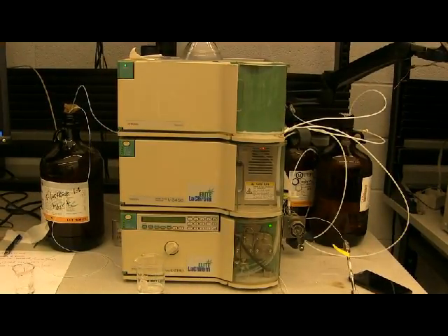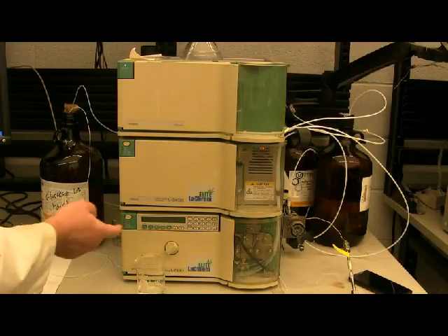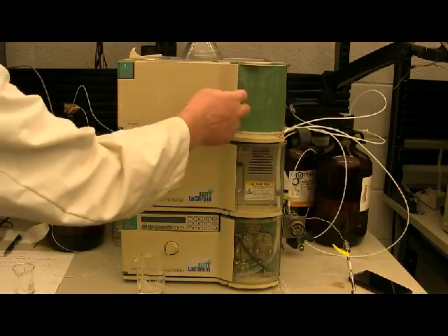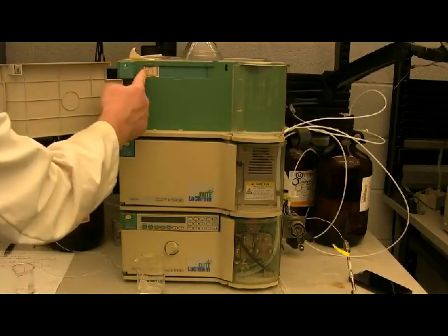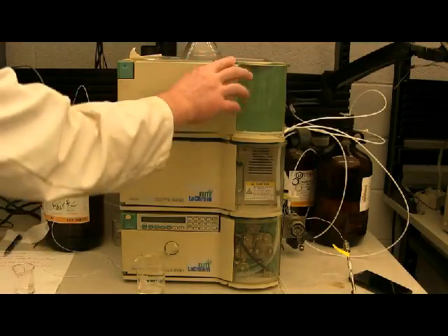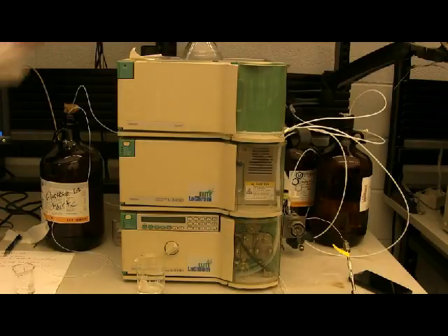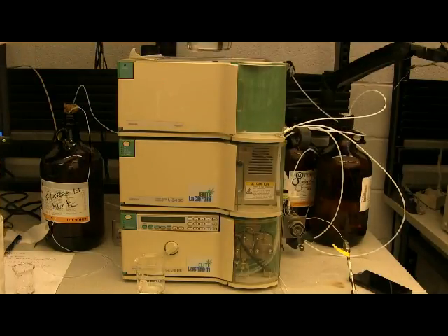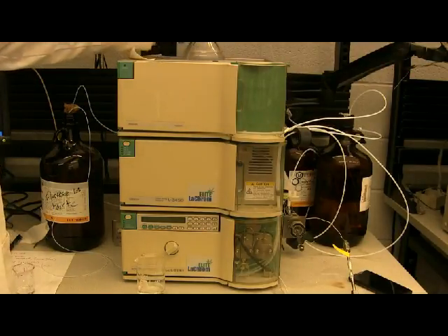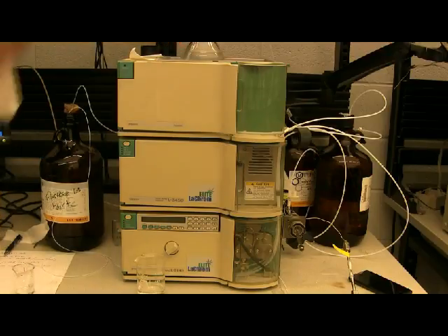And then to shut the instrument off, it's just the reverse of how we started. Pump off first, then the diode array detector, then the power. You always want to make sure that there's plenty of mobile phase left for the next lab. You never want the mobile phase running dry.